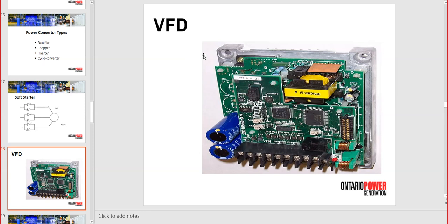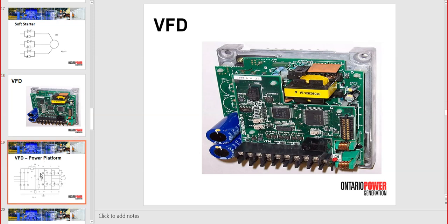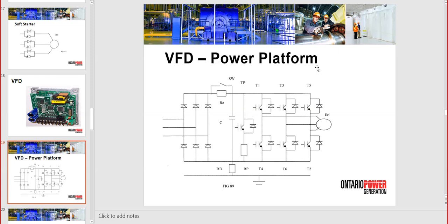Okay, a VFD for a very low 2 horsepower motor. You see the blue capacitors are actually the DC bus capacitors, and then you have a main board that is on top of the IGBT, 3 blocks, 1 per phase, and then you have a small piggyback board with the CPU that has the control. The main board with IGBTs has a power supply, and then you have protections and everything that is directly controlling the IGBTs, the gates and everything else. Okay, so it's very compact. This is a Yaskawa drive, very high performance. Siemens, Yaskawa, Mitsubishi I like because it's lower price and has the same performance or better. So there are manufacturers that are fully trustworthy and with a good record of VFD manufacturing, good OPEX.